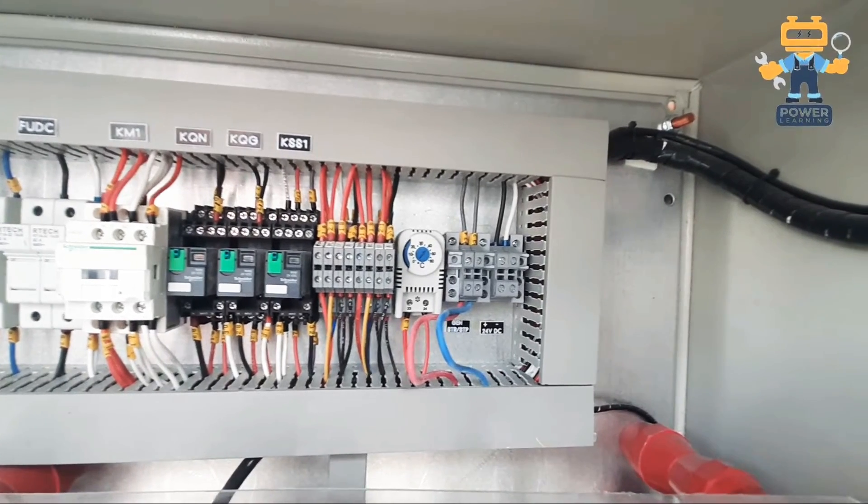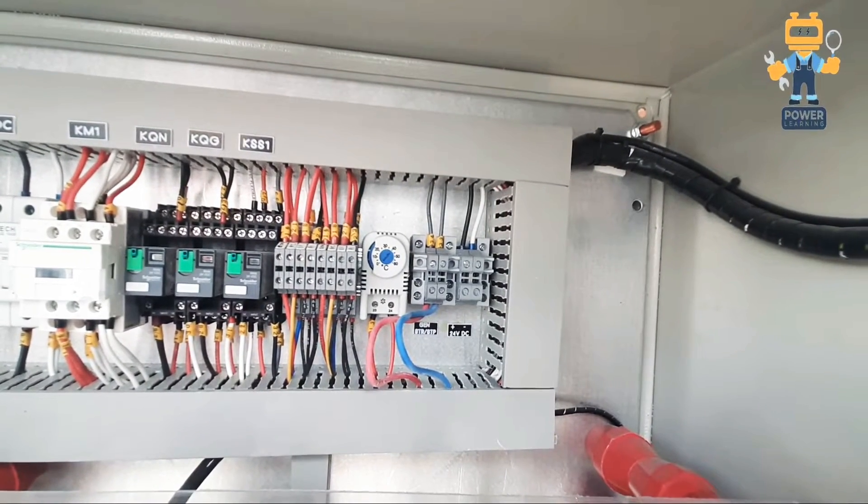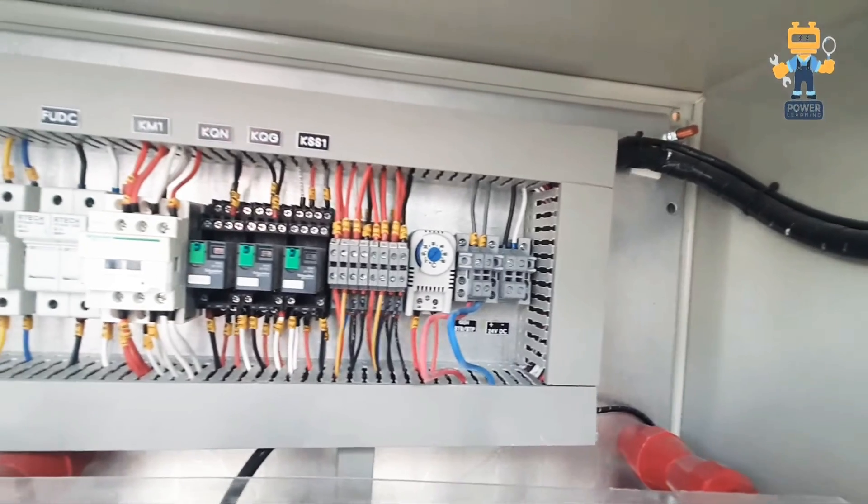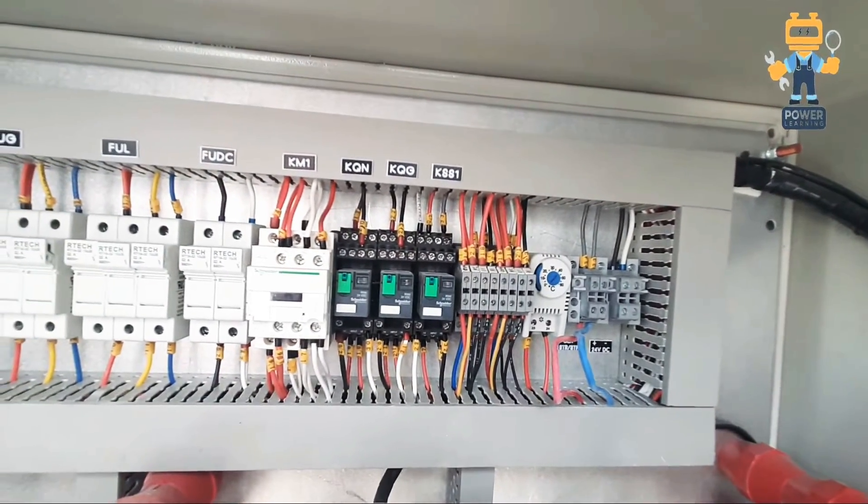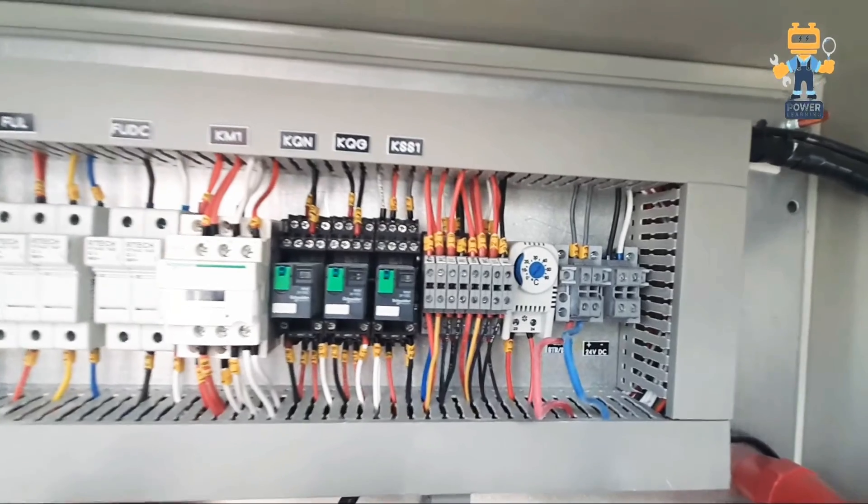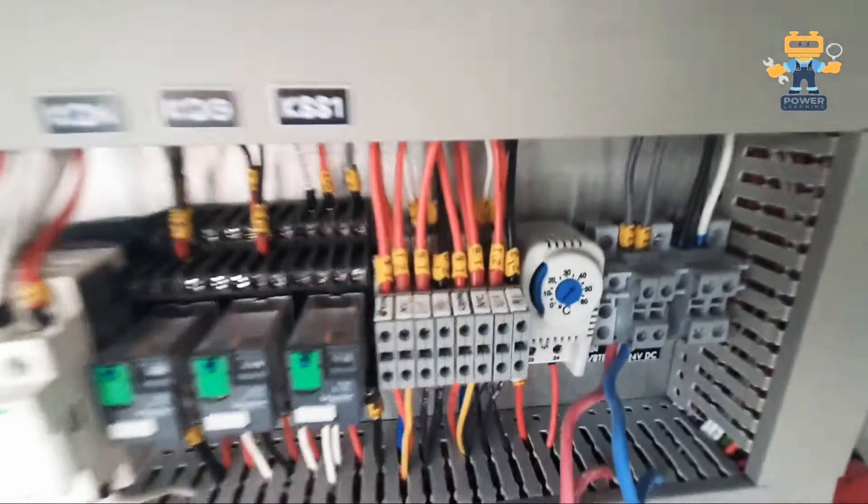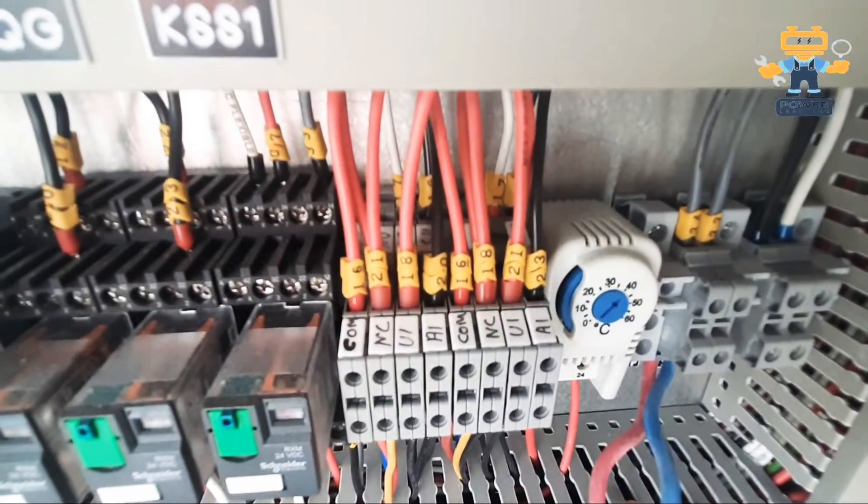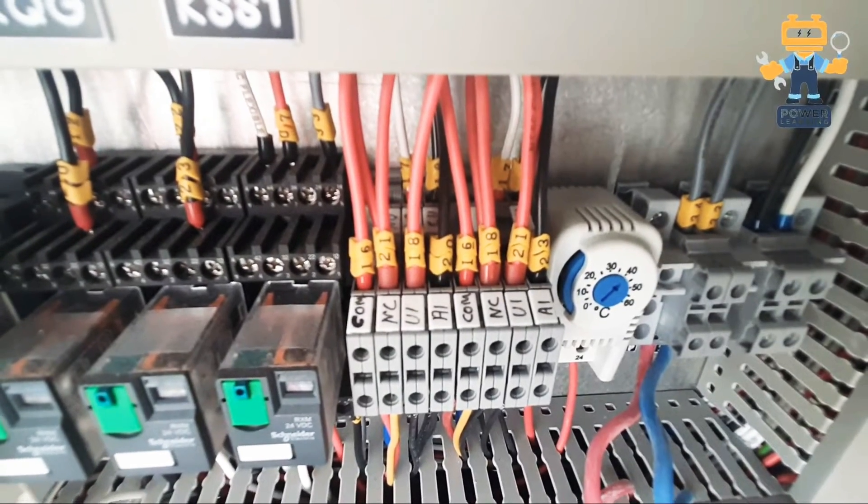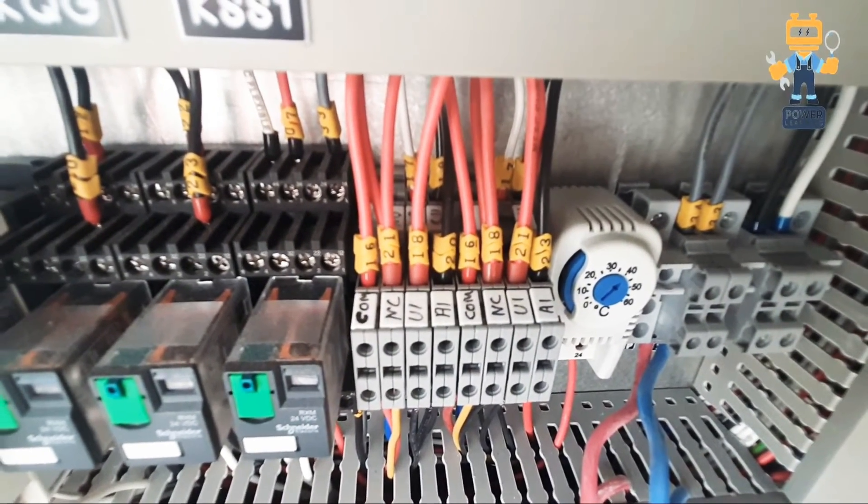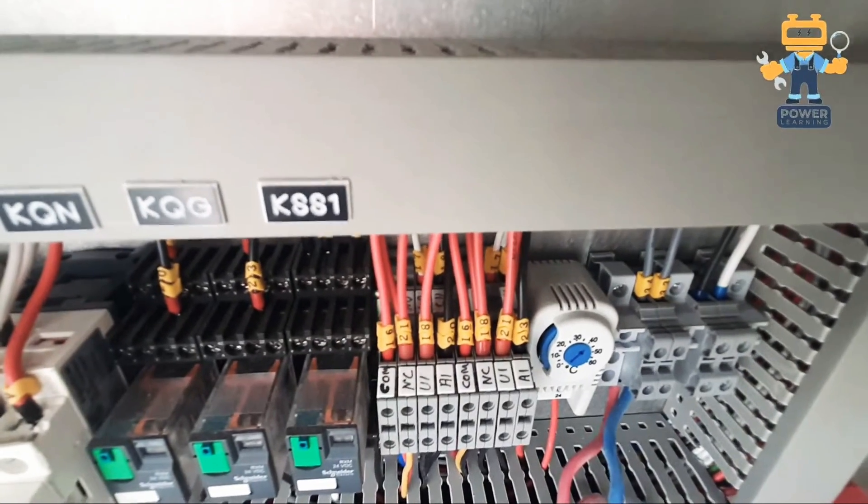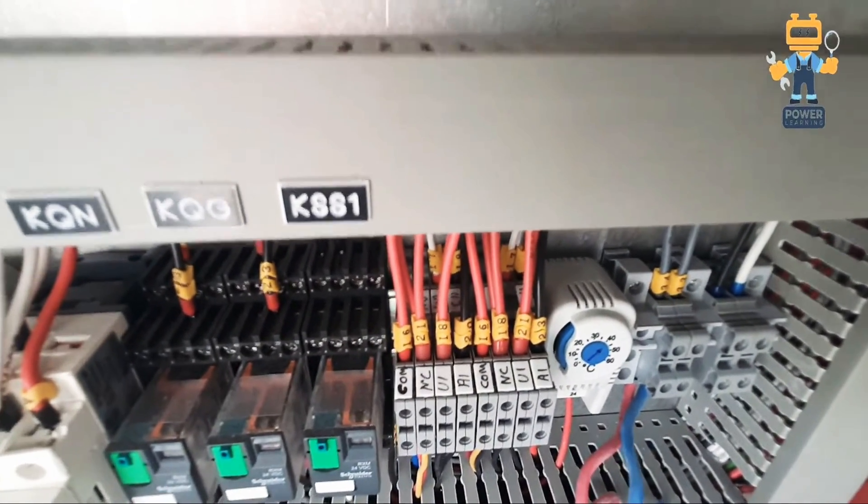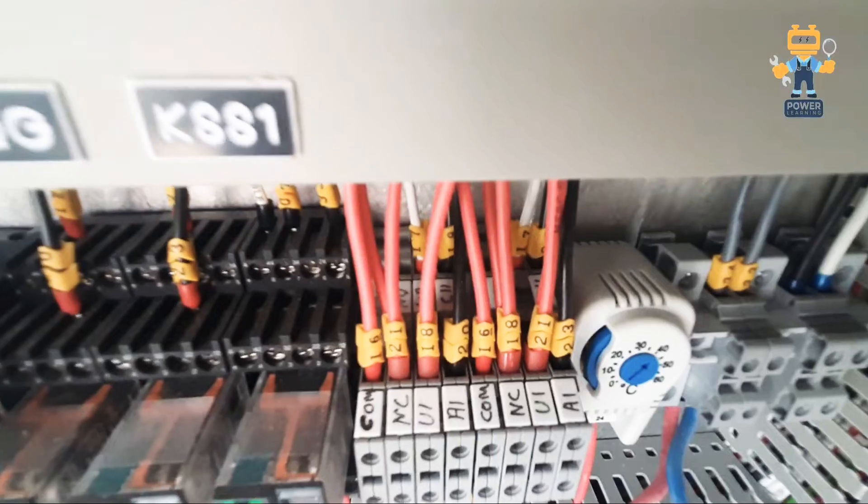These terminal connections are for our motor mechanism. We take out all the motor connections here on the terminal point and we terminated all the control cables and connected with the motor mechanism. As you see these are the numberings of the motor connection, so easily we can replace this motor and remove the cables from here.